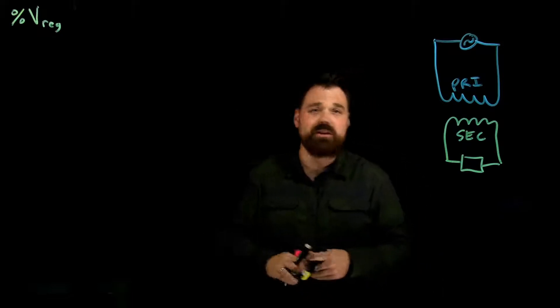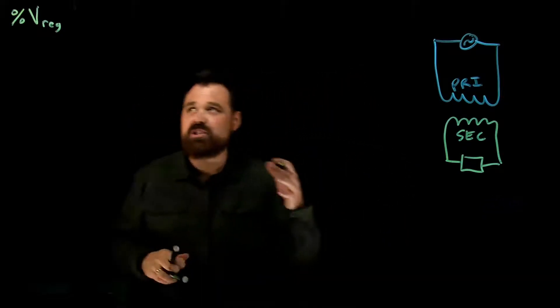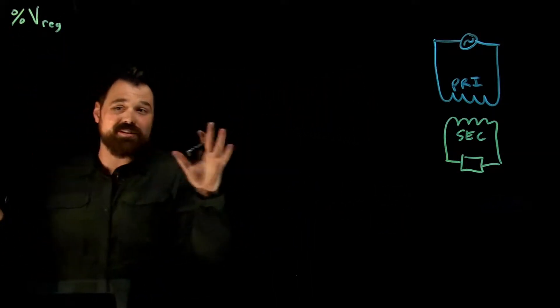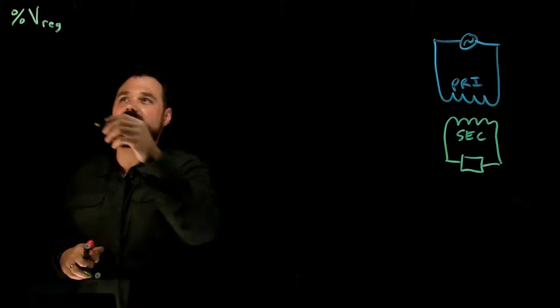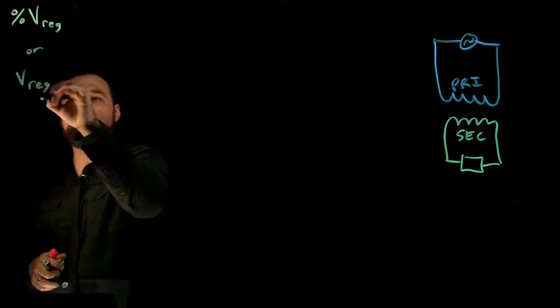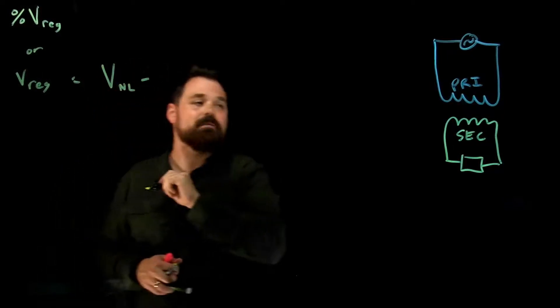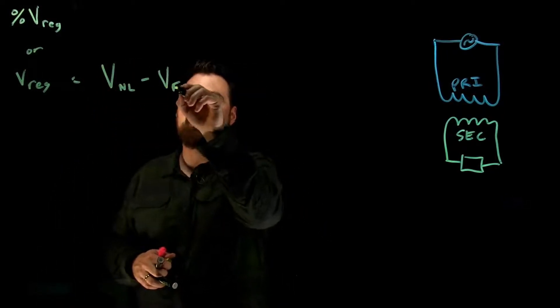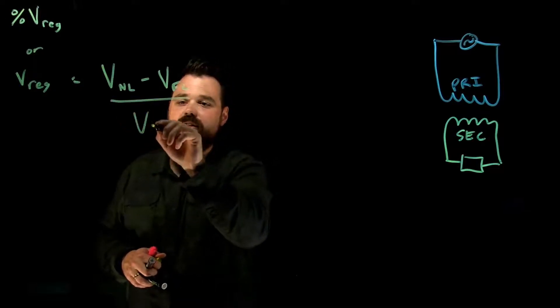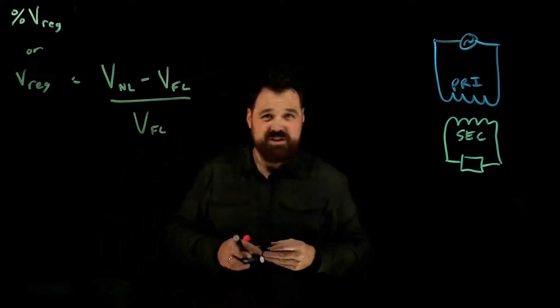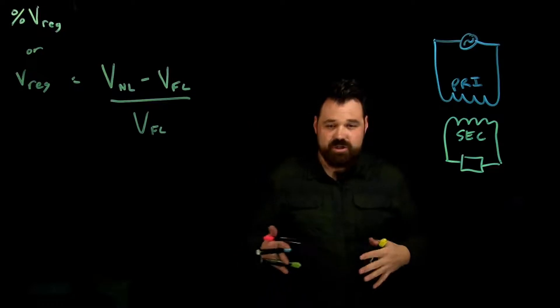So what our formula looks like is we have our percent voltage regulation, or V-reg voltage regulation. It equals the volts no load minus the volts full load over volts full load, which is a similar concept to speed regulation on a motor.